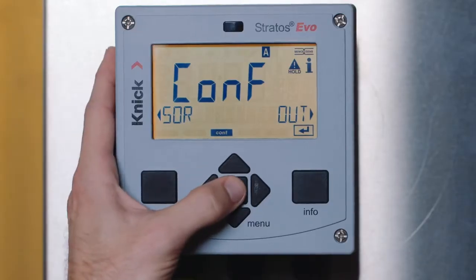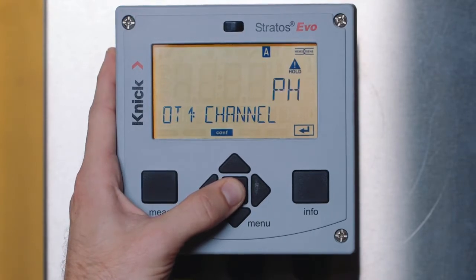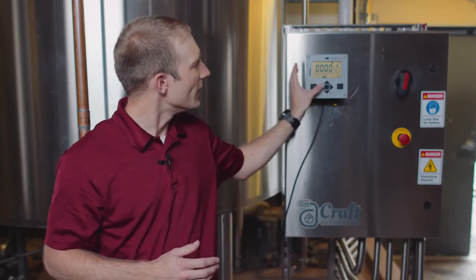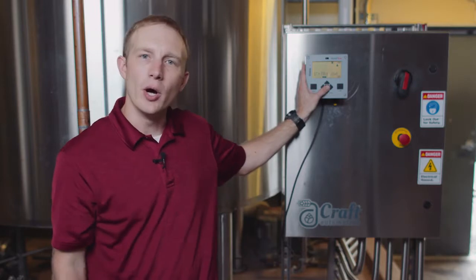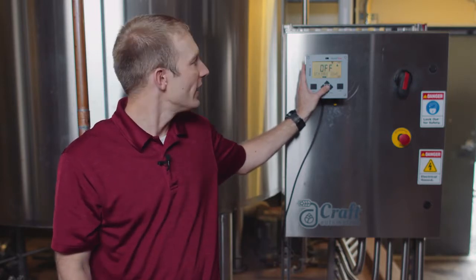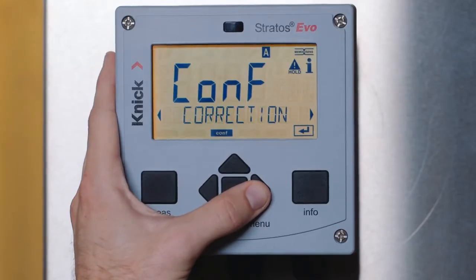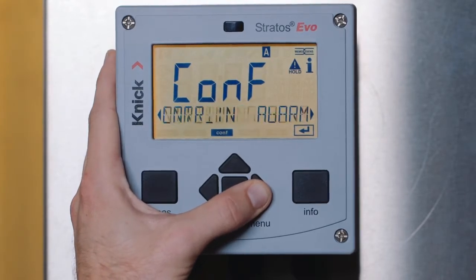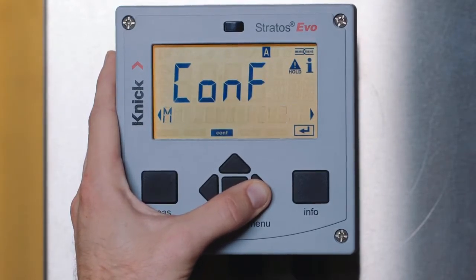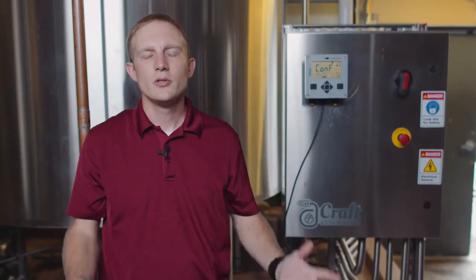Here, you have the ability to set up the two 4 to 20 milliamp outputs provided by the Stratos Evo transmitter for our desired pH and temperature range. Within the output configuration, we can also apply a filter time for dampening, as well as set the failure mode to drive the output to 22 milliamps. Toggling to the right, you can also see the additional features and relays that can be configured within the Stratos Evo. Two very important menus that should always be configured are the alarm and clock menus.